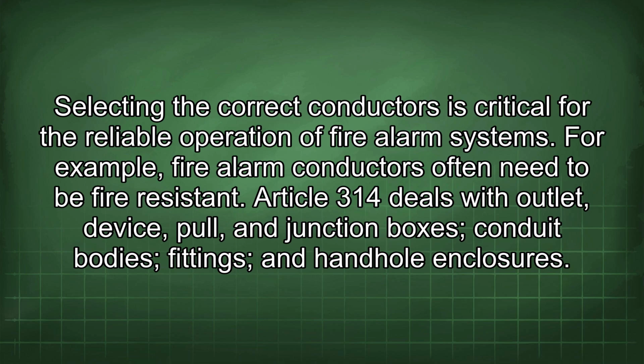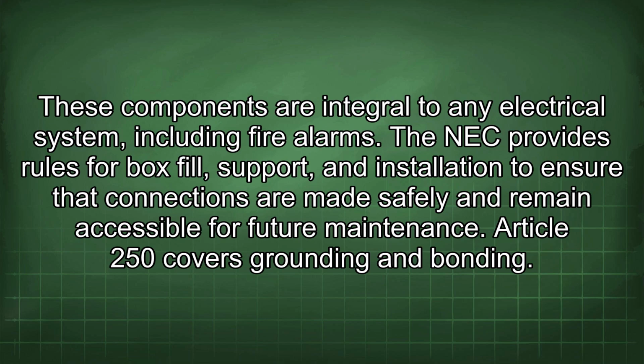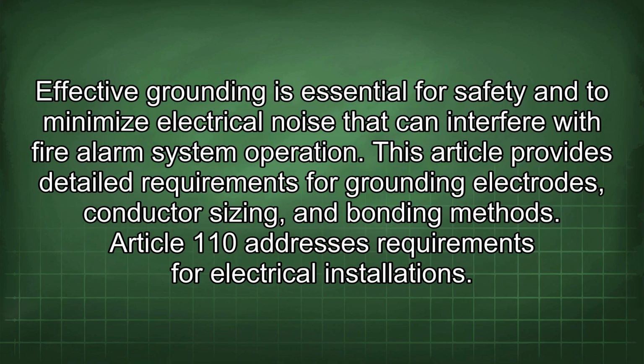Article 314 deals with outlet, device, pull, and junction boxes, conduit bodies, fittings, and handhole enclosures. These components are integral to any electrical system, including fire alarms. The NEC provides rules for box fill, support, and installation to ensure that connections are made safely and remain accessible for future maintenance. Article 250 covers grounding and bonding. Effective grounding is essential for safety and to minimize electrical noise that can interfere with fire alarm system operation. This article provides detailed requirements for grounding electrodes, conductor sizing, and bonding methods.